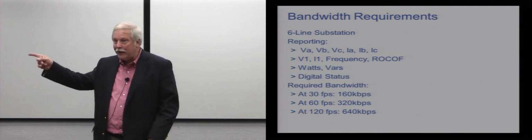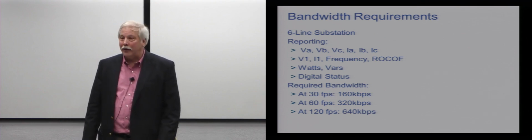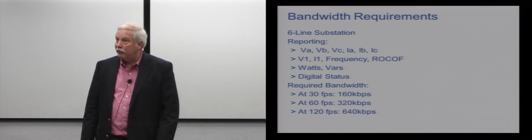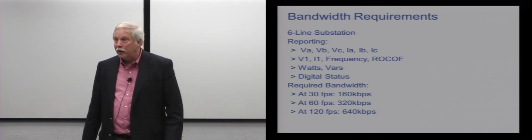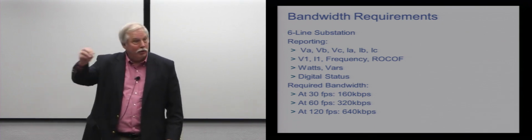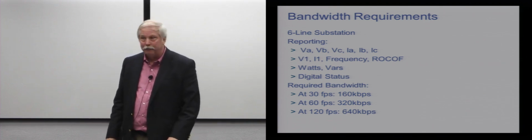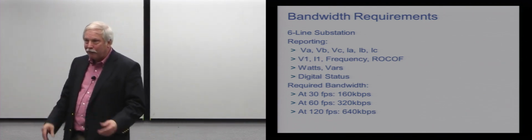On the high end, if I go to 120 frames per second, I now need 640,000 bits per second communication from my substation to my remote locations. So that's why today's power system engineer also has to be a communications engineer.